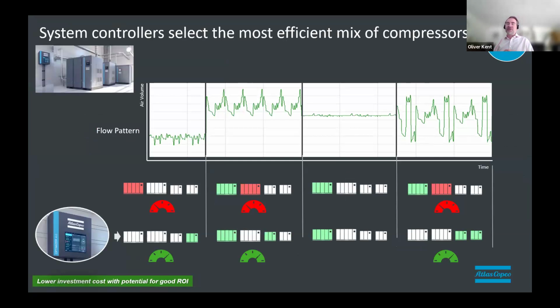And then system controllers. Okay, so we might have a compressor room with several compressors in it. Ideally, we don't want those compressors all just running independently, doing their own thing. We want to pull those compressors together under a single controller so that our compressed air system is running as one coherent system. Here we've got an example of the sort of performance benefits of using what we would call a central governor. A central governor is quite a sophisticated compressed air controller, designed to control multiple compressors of differing sizes.